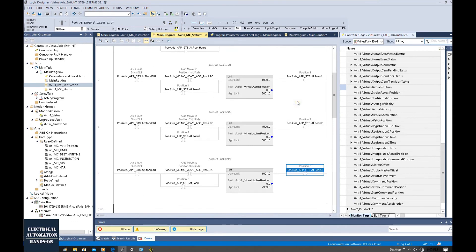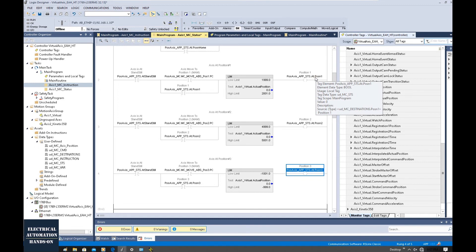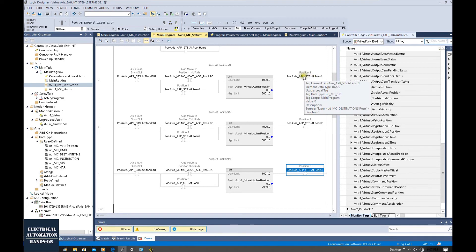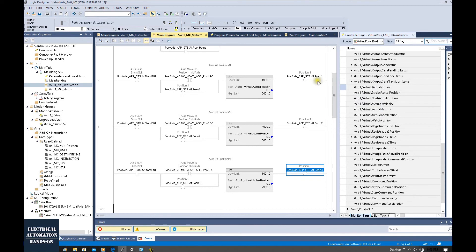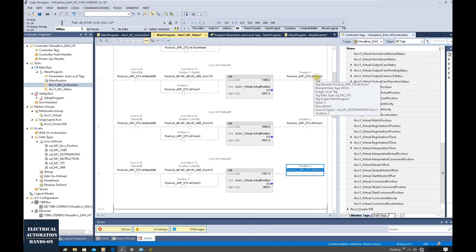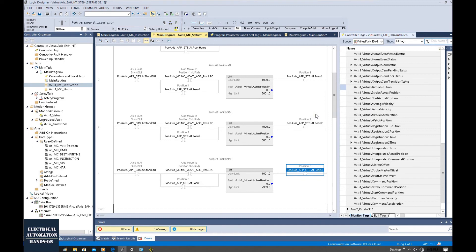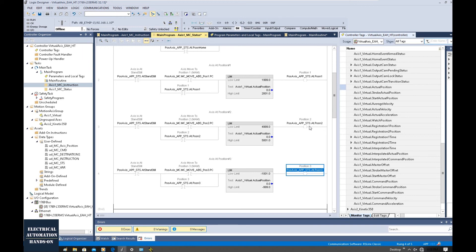The at-position signal would be used for multiple purposes. One typical way we will use is for sequence control. As we know, the MC instruction, we better control or execute the motion control command one time, one command. Once one command completes, and then we trigger the next one. So the best way to organize this is using sequence control. How can we judge one command finished or complete, and the axis arrived at that position? That is this signal. So the basic idea is we trigger this command, and then wait for this feedback, and then we move to the next step, execute the next command, trigger the next instruction. Do this one by one. This will prevent us from overlapping, triggering two instructions at the same time.